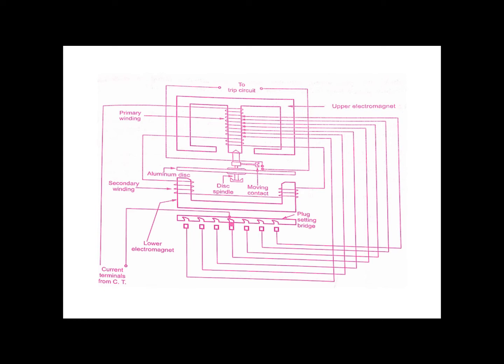There are usually seven sections of tapping to give an over current range from 50 percent to 200 percent in steps of 25 percent. These values are percentages of the current rating of the relay. For example, a relay with a current rating of 10 amperes can be connected to a CT with a secondary current rating of 10 amperes.